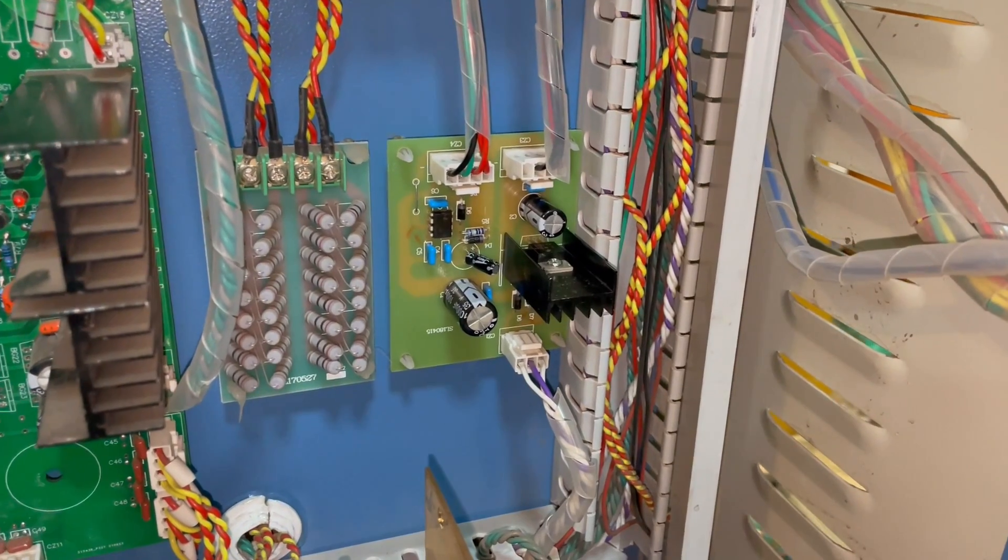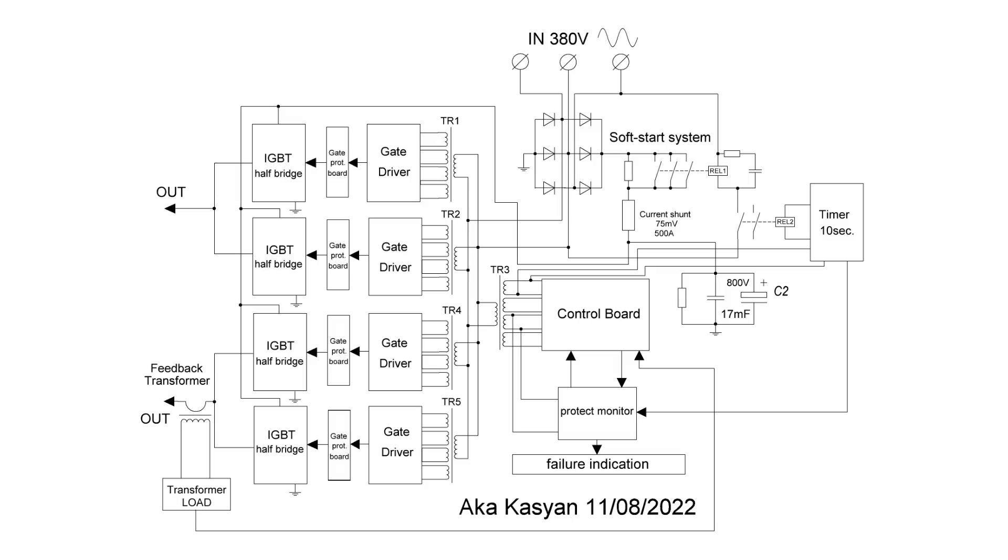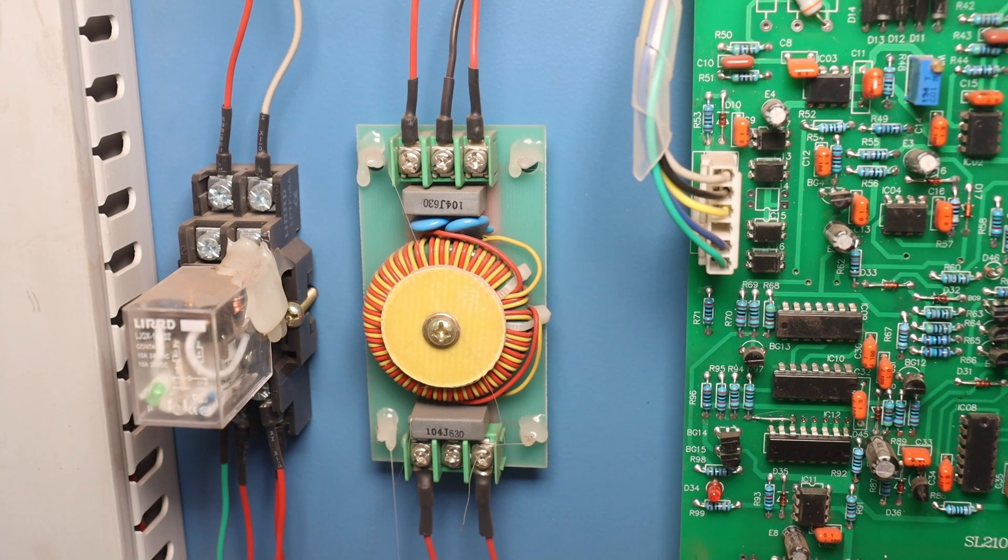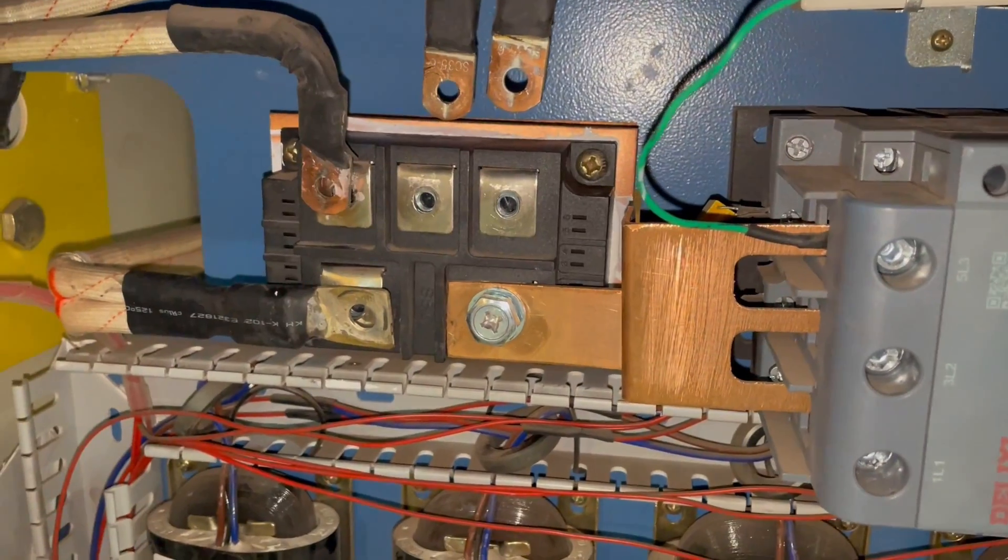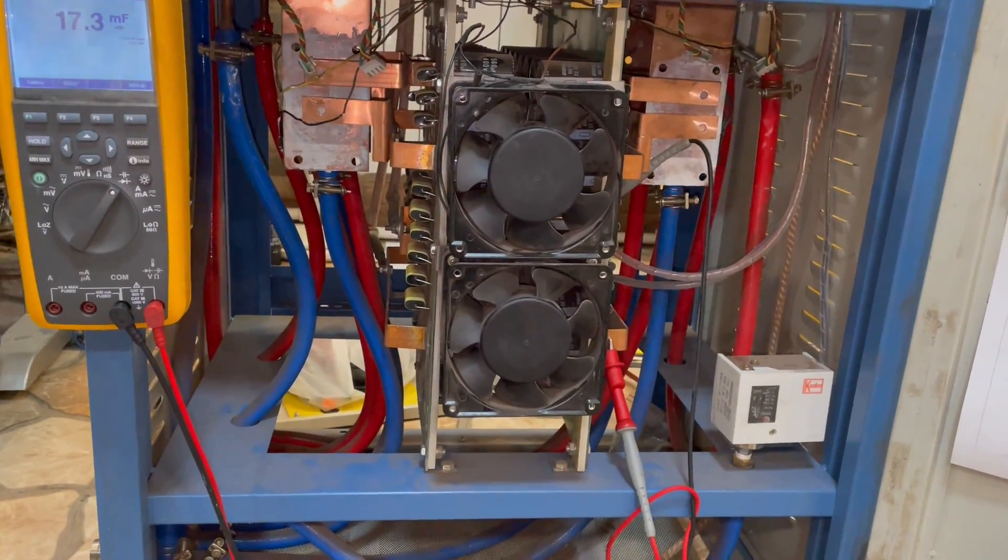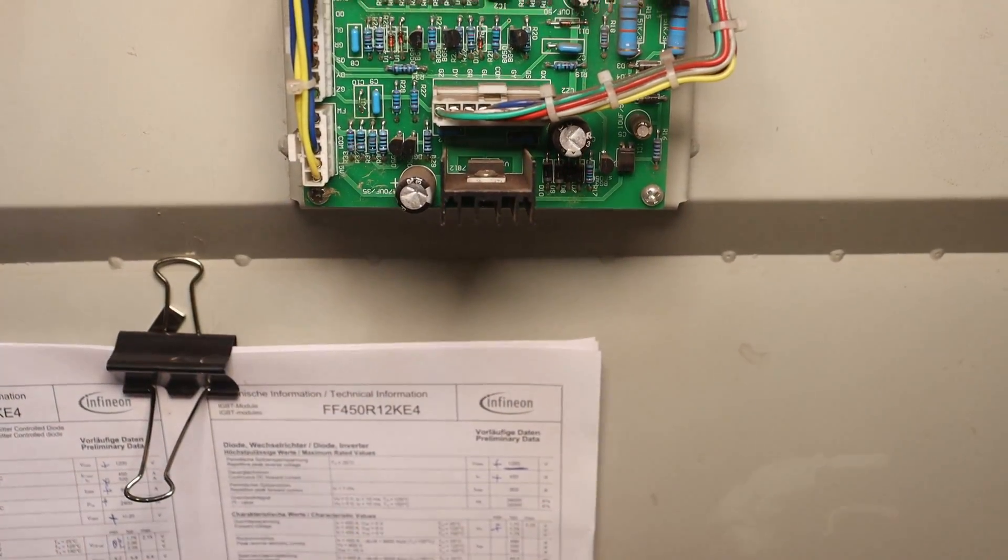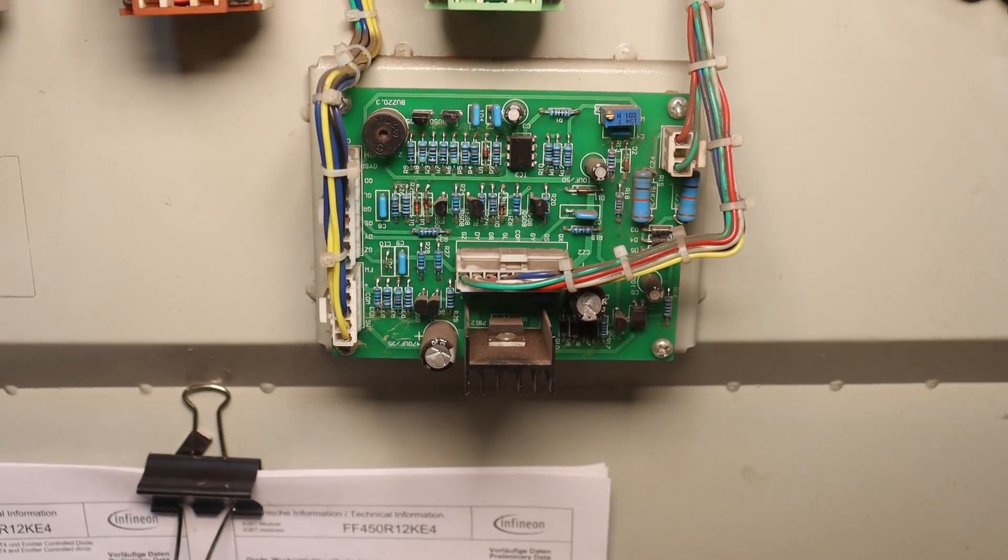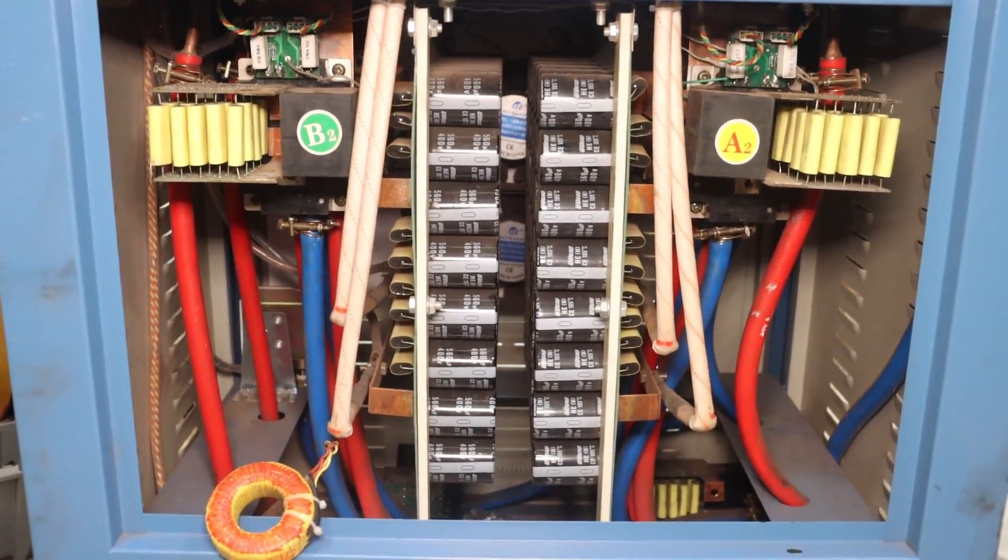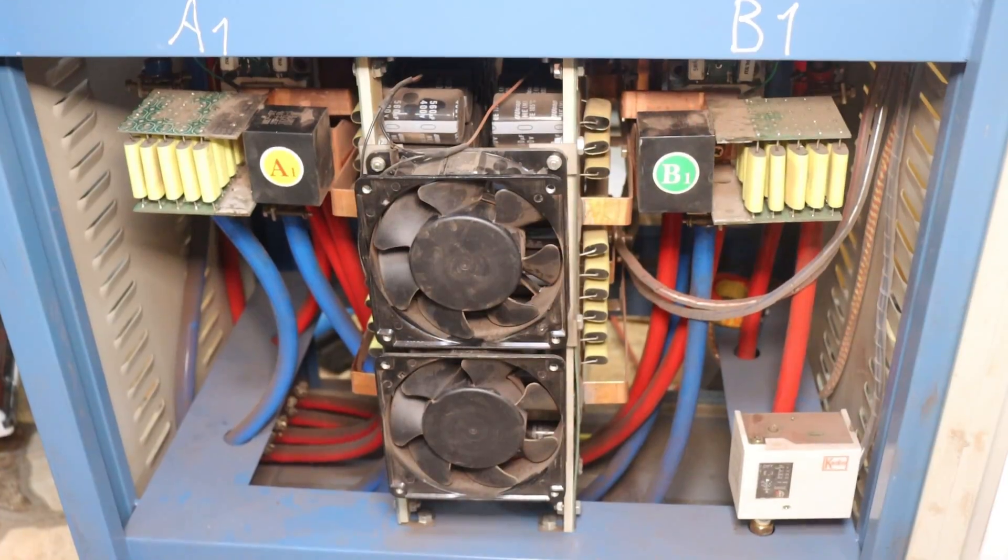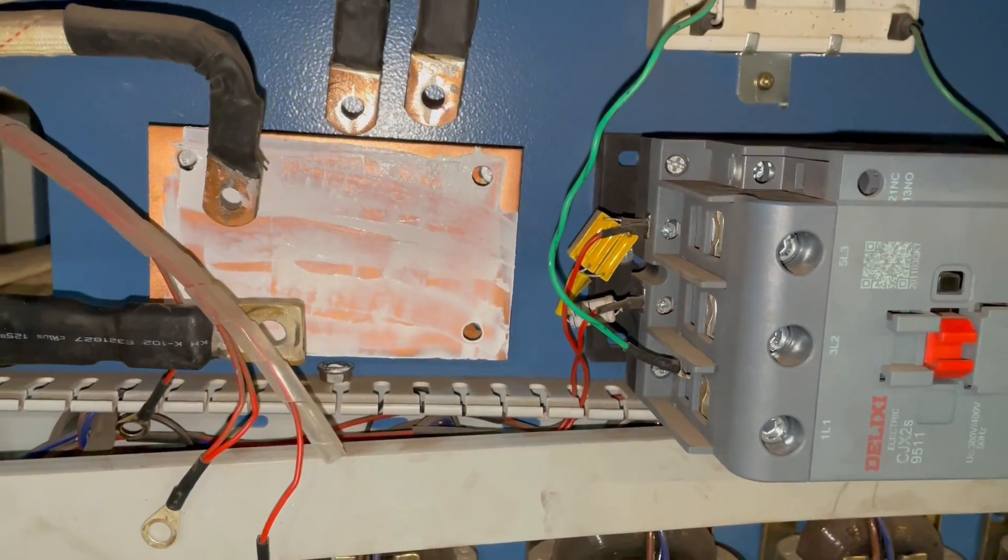On this board is assembled a timer on a 555 microcircuit. After 10 seconds the timer will work, turning on this relay, which in turn switches the power supply to the winding of a powerful starter. As a result, now all the current from the bridge goes through the closed contacts of the starter. The board on the front panel makes monitoring from all sensors. There are at least four thermal sensors, a current sensor, a water pressure sensor, power voltage monitoring, phase control and so on.